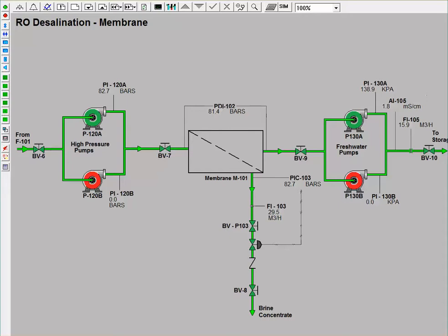The pressure of the salt water entering the membrane is controlled using a pressure controller and is maintained at about 82.7 bars. At design conditions, the clean water product is at a salinity of 1.8 millisiemens per centimeter, which is much lower than the salinity of the feed.